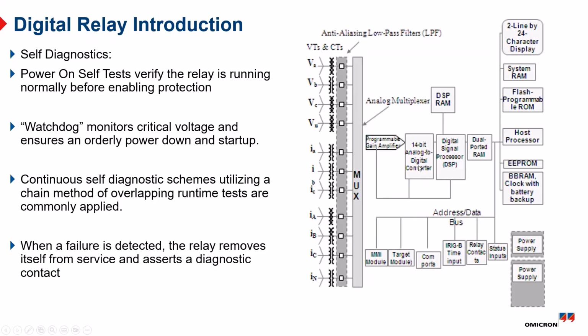It's basically a daisy chain of devices. The A/D converter has to stay online. It's also a computer, a microcontroller, in that as well. Also, the DSP has to toggle a bit to the host processor every clock cycle to tell the host processor it's still running. And then there's a watchdog chip that watches the host processor and makes sure the host processor is still running, and monitors the critical voltages on the board, called VCC. So if the voltage at the board went to an unsafe level, the watchdog would put the processor in reset and hold, to make sure the relay didn't misoperate if the battery went dead.